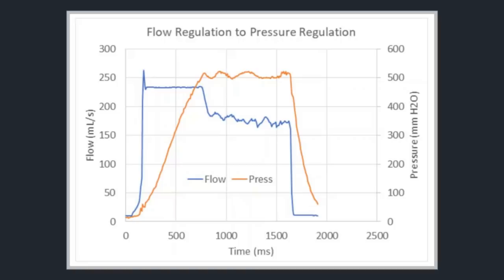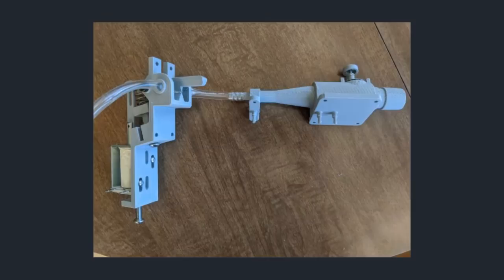Here is a measurement showing the OpVent delivering constant flow followed by constant pressure. Here is the open source proportional solenoid valve on the left and venturi flow meter with pressure relief valve on the right.